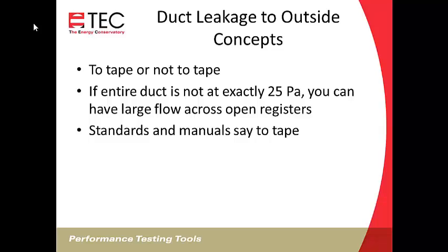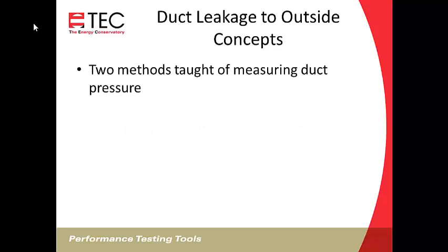All of the blower door manufacturers' manuals and their test procedures say to tape, and standards like the RESNET Chapter 8 standard say that you are required to tape during the duct leakage to outside test. There are two methods being taught for measuring duct pressure during the duct leakage to outside test: the duct to house pressure and the duct to outside pressure.